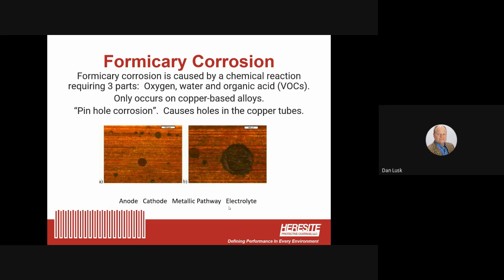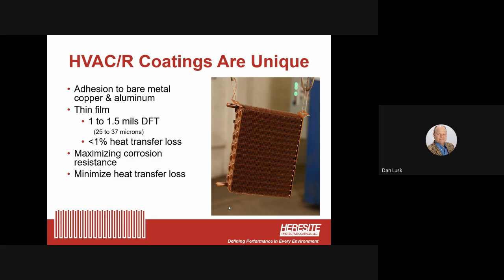It's important to note that HVAC coatings are unique. They have to adhere to bare metal, usually copper and aluminum, without a primer. And they go on very thin, 1 to 1.5 mils dry film thickness, about 25 to 37 microns, while still performing with maximum corrosion resistance. The reason they go on so thin is to minimize heat transfer loss, so the heat exchanger performs the same with or without the coating. There's less than 1% heat transfer loss using our coatings to protect a heat exchanger.